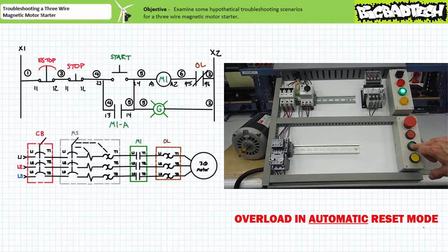The triggered overload element signals the contactor to open as expected. When the overload element in automatic mode cools and resets, when I stop triggering it, the system does not immediately start since the holding circuit has dropped out. Only when an operator makes a conscious decision to do so by actively pressing and releasing start, does it do so.